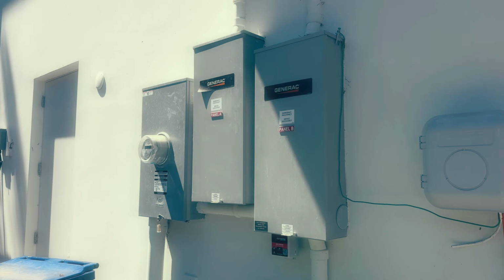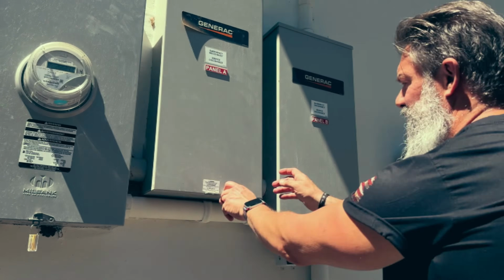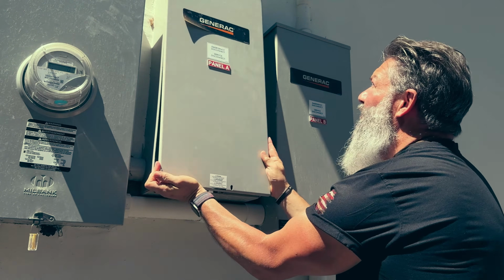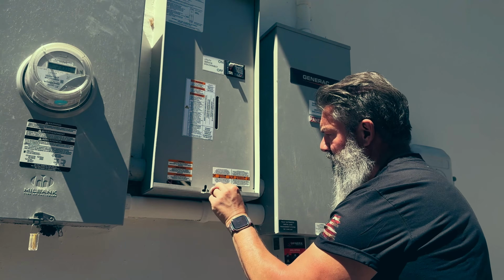Locate your automatic transfer switch. It's usually mounted near your main electrical panel. Remove the front door single locking screw, and trust me on this, screw it right back into the hole you took it from. If you set it down, it will pull a Houdini and disappear forever.